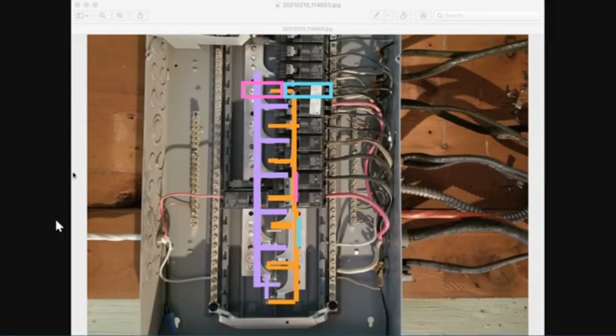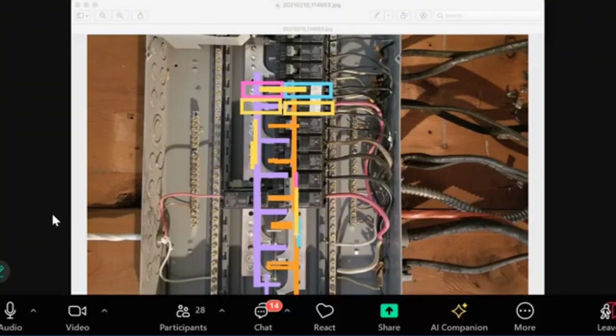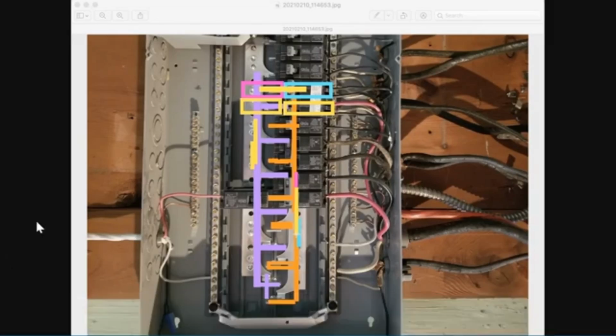If I put a breaker just below that one, this breaker makes contact with this bus bar. But it goes into the middle, so if I put a breaker here, now both of these yellow breakers are making contact with this bus bar. Both breakers right above are making contact with this bus bar. Does everybody see how that works now? Are we getting a better visual?